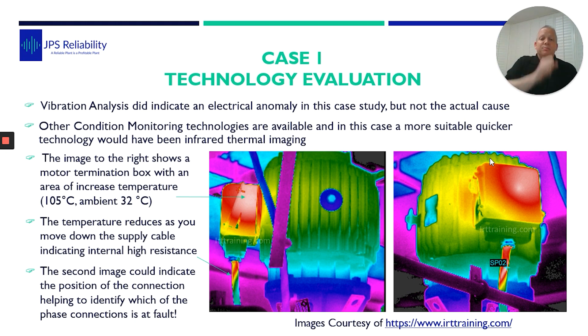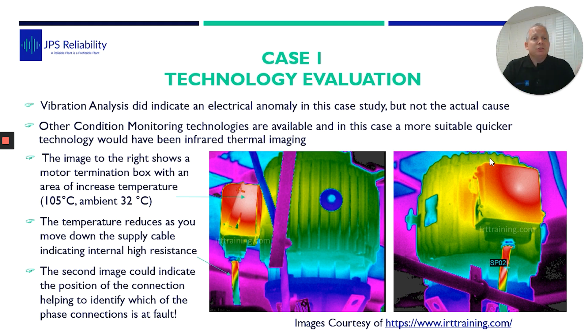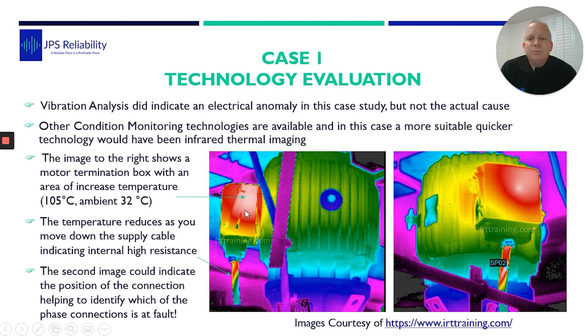Here's an image I got from my good friend Austin Dunn from the IRT trainer. So if I had a thermal camera on this particular job and scanned the motor, this is what I would have seen for sure. This shows the terminal box at 105 degrees with 32 degrees ambient. And one important thing to notice: as the temperature comes down away from the terminal box, it reduces. So you know it's not overloading — there's a problem right there at the connection.